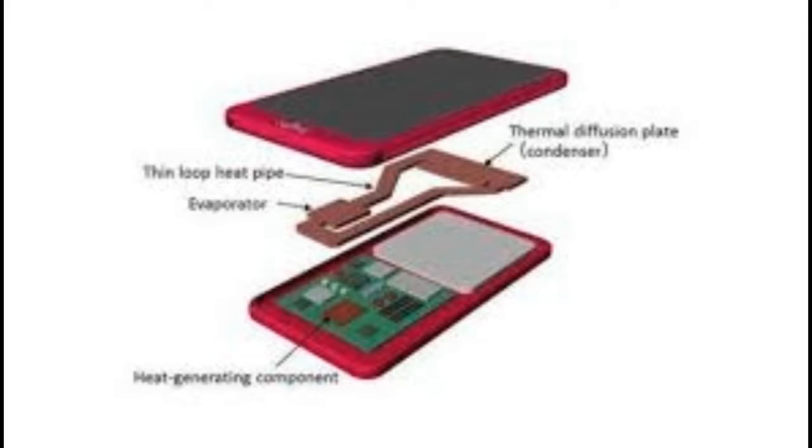The liquid used in cooling may be de-ionized water or an electrically non-conductive and non-capacitive engineered fluid, of which there are a number of patent formulations. You can't use tap water as the ions dissolved in it are likely to corrode the water blocks. For the same reason, it's inadvisable to mix metals in a cooling loop.